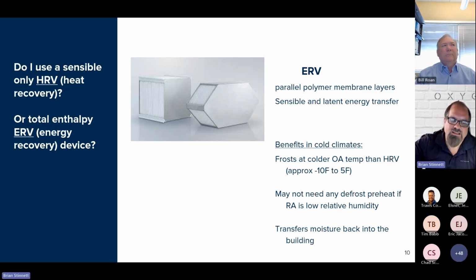So I don't have to bring in that cold, super dry air, because I'm going to transfer whatever moisture, about 60 to 65% of the moisture of the exhaust air is going to be transferred over to the incoming outside air and brought back into the building. So it helps not only occupant comfort levels, because it keeps some moisture in the building in the winter, also helps with finishes. You don't get such dry conditions for the wood, etc., the finishes in the building. So a few advantages to using an ERV in a cold, dry climate like Denver, even though you don't have to be concerned about humid summertime.